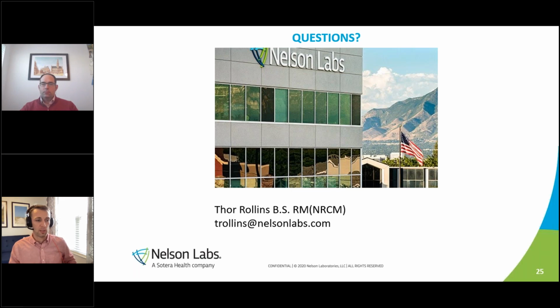One is, with the increased focus on the whole life cycle of the medical device in MDR, how much importance should we be putting into evaluating processes like manufacturing residuals, additives, mold release agents, finishing agents, and downstream processing? How much of this should be evaluated in the biological evaluation plan and report?